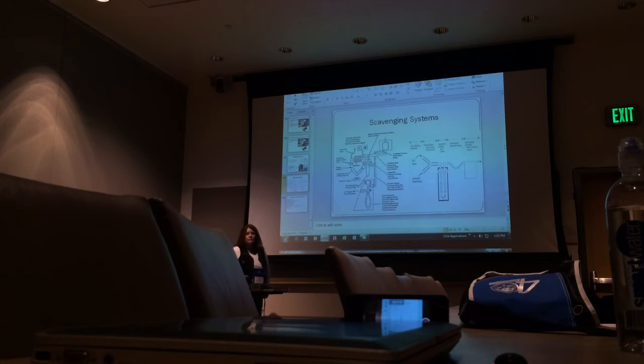You turn this off, gas is still going into it, and you'll start to smell agent after a while during a case. The old style open reservoir scavengers made a horrible hissing noise that would drive people crazy. And they would be tempted to turn them off, and then you get a call from biomed telling you, there's a leaking vaporizer up here, we smell agent through the whole room. And we're going to cover this in the next section.